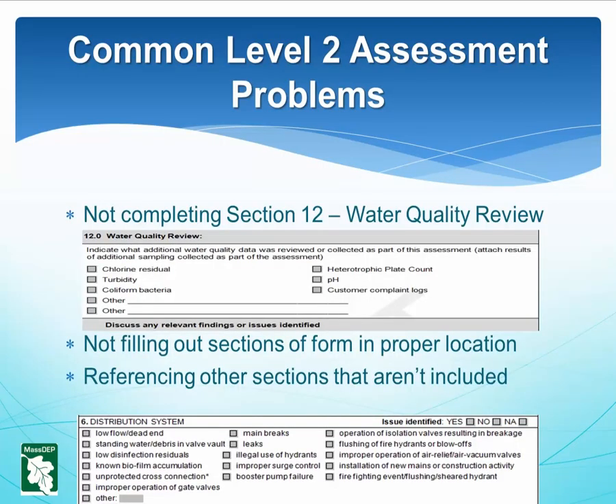Common Level 2 Assessment Problems: A common problem is not completing the required Section 12 water quality review. Water quality data should be compiled and evaluated as part of all Level 2 assessments. The data reviewed will vary by situation but may involve special purpose coliform samples, chlorine residuals, disinfection byproducts, or HPC, among others.